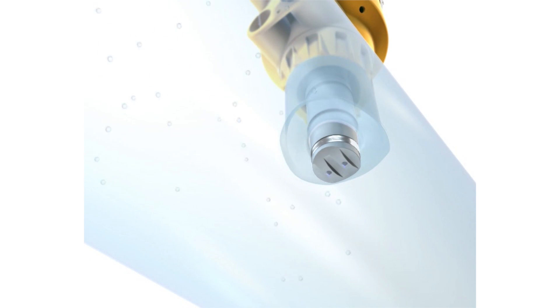The device creates an alternating magnetic field by means of a built-in coil. The magnetic field interacts with the flowing liquid and generates a small voltage across two measuring electrodes. The voltage is proportional to the flow velocity and is measured and processed by the integrated electronics.